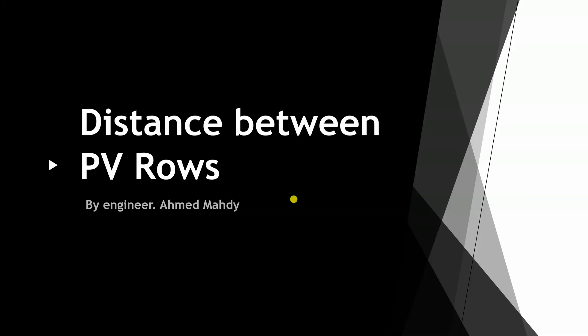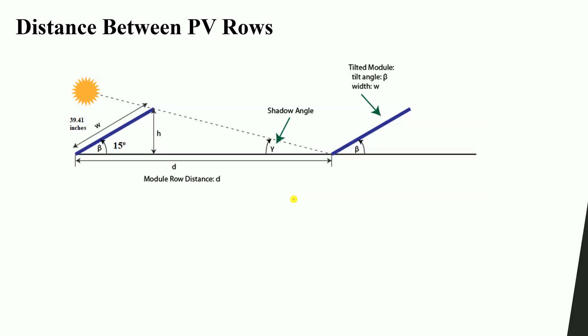Welcome everyone. In this lesson we will talk about the distance between PV or solar panel rows. As we mentioned before, each row of panels requires a distance between them to avoid the shading effect. This distance is approximately three to four times the height of the panel.